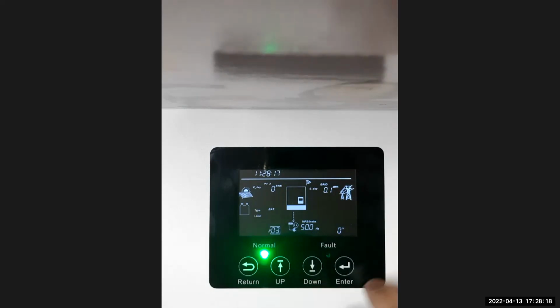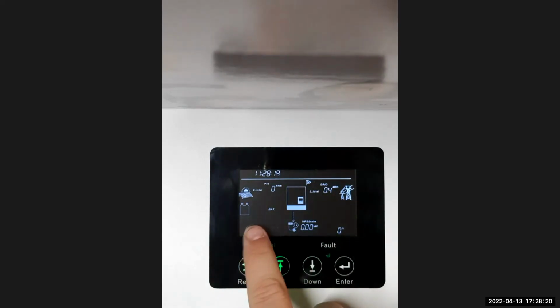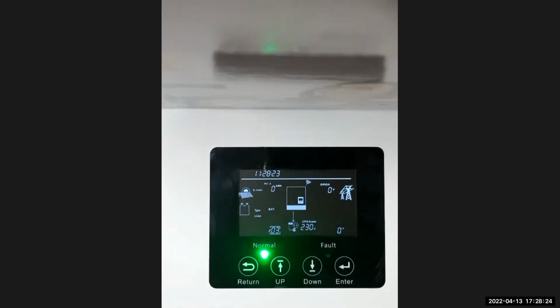You can go to the up button, then it shows you lithium ion. So that's when you have a lithium ion battery that can communicate, or no battery. You can use this unit without any batteries as well. So it will function then as a grid tie type of inverter, that it will use Eskom and the available amount of power from the panels to supply the load to the house. It will function like that, but it's not that effective as a fully hybrid with that specific function.